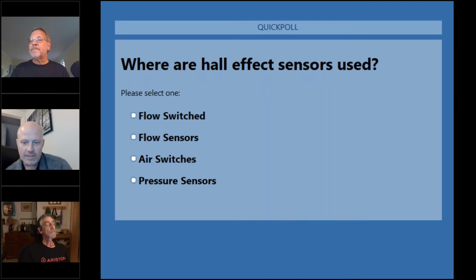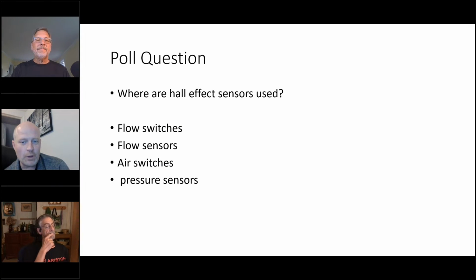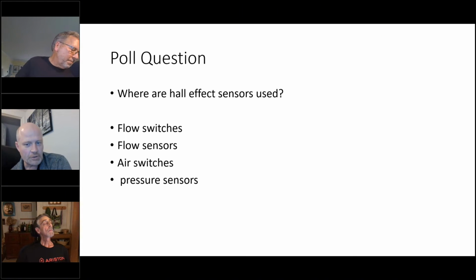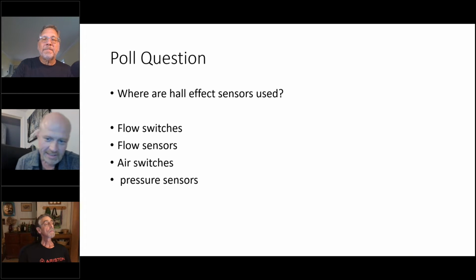Okay, so flow switches was 13%. The correct answer is 69% for flow sensors. For the people that said flow switches, you may be thrown off by the magnet, and in a flow switch, there typically is a magnet, but it's used in a different way. So we're going to talk about that in just a second. There are no magnets in air switches typically, and typically there's no rotating component, although it's possible that you could use a Hall effect sensor to measure airflow, for example, using one of those, oh, help me out, Ted, what are those things? Anemometers, the ones you stick in the airflow and it spins the little blade. I'd be willing to bet that any digital version of that has a Hall effect sensor in it.